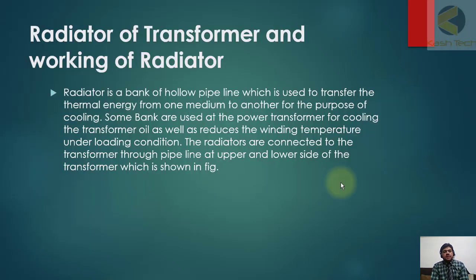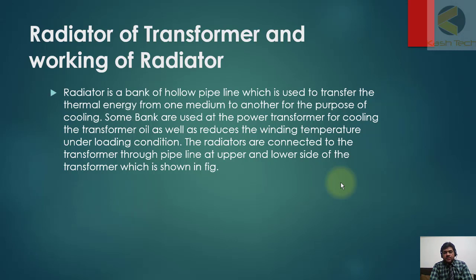Welcome back. We move to the next topic: radiator of transformer and working of radiators. The radiator is a bank of hollow pipelines which is used to transfer the thermal energy from one medium to another for the purpose of cooling. Some banks are used at the power transformer for cooling the transformer oil as well as to reduce the winding temperature under loading condition.